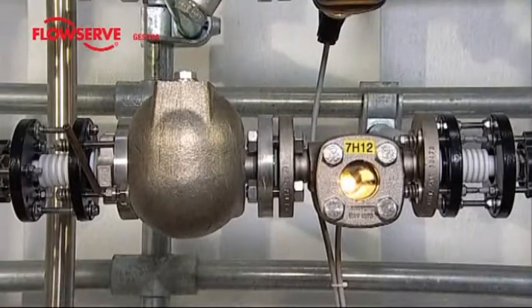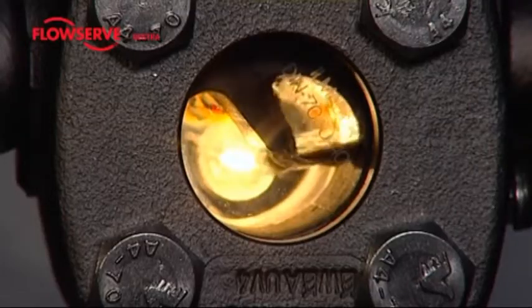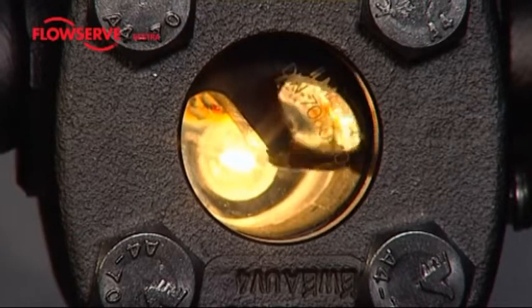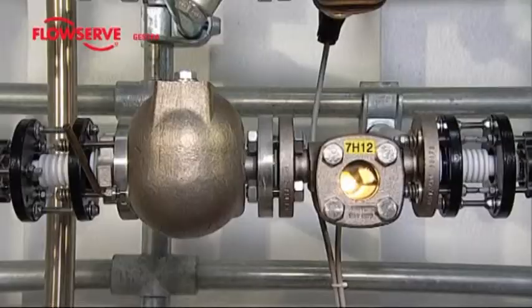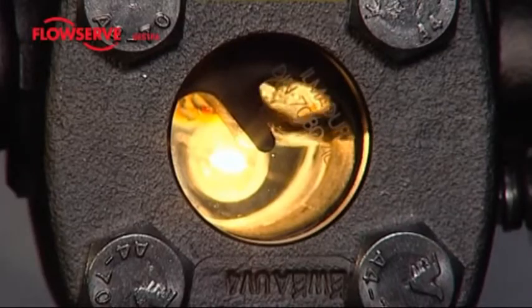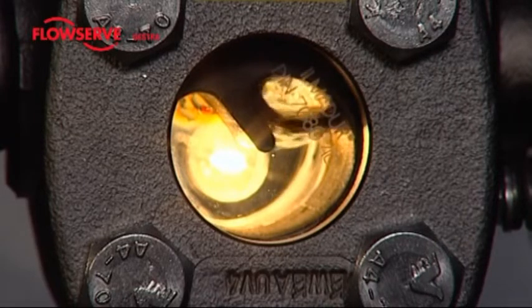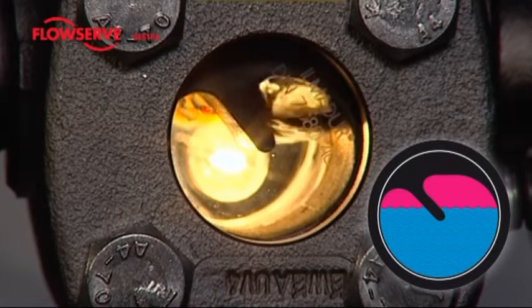The float trap is preceded by a special sight glass, the Vaporscope VK16. This is used for monitoring the steam traps and making the flow processes visible. A deflector inside the Vaporscope sight glass forces the condensate to flow through a small siphon. A small steam space is formed in front of the deflector, and the deflector is slightly immersed in the condensate.